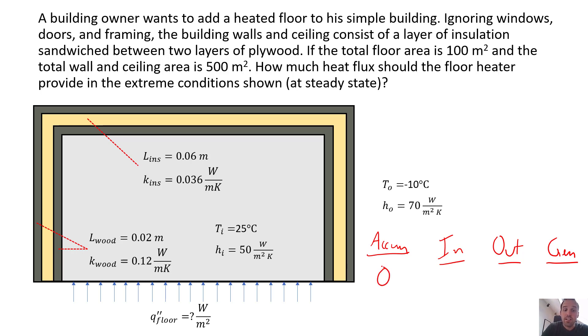We're going to design this heater system to maintain a steady state indoor temperature of 25 when the outdoor temperature is minus 10. Okay, in terms, so we could treat this heated floor as an in term. We could treat it as a generation term and that would sort of just depend on how we define our system boundaries.